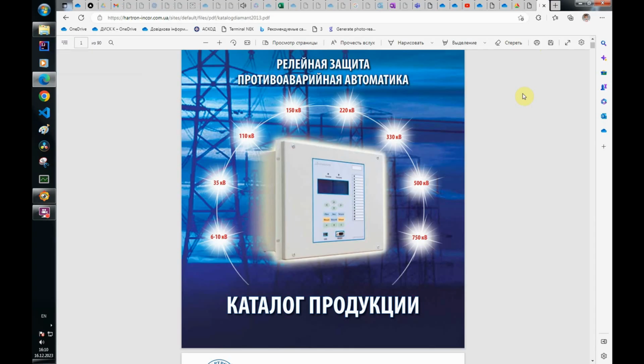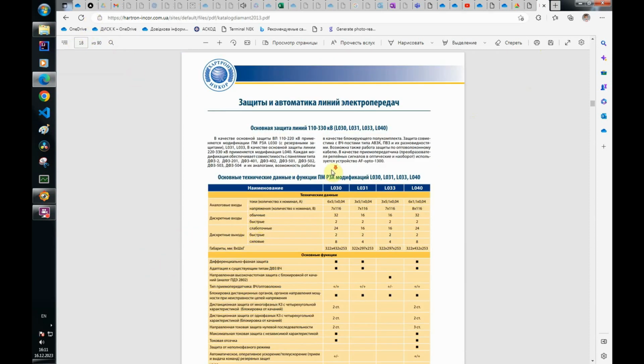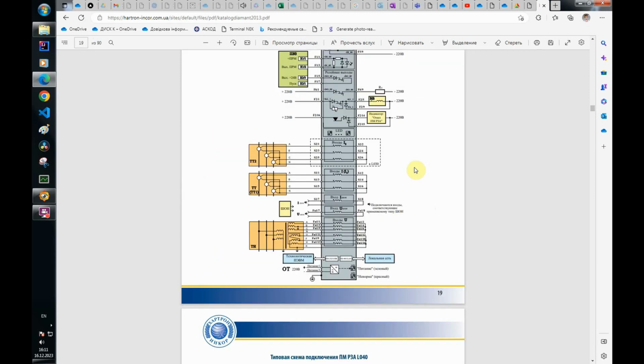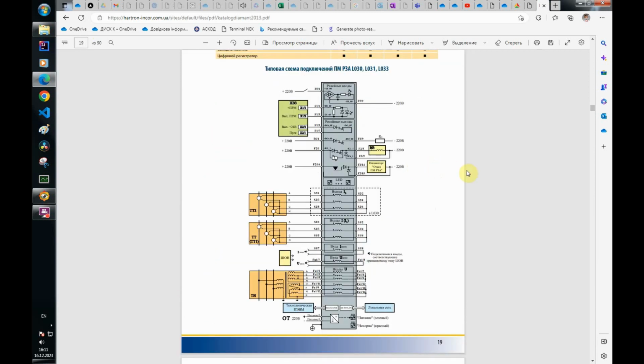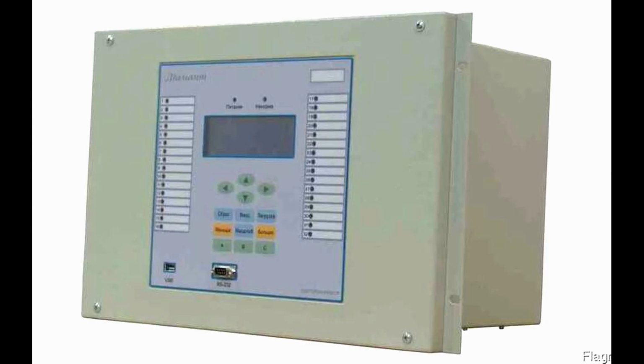I'll open the product catalog. In the case that I will consider, the L030 device is used. This is an IED that performs the functions of phase differential protection and backup protection. The set of backup protections for the device is limited: 2 zones of distance protection, 2 steps of zero-sequence current protection, and current cutoff. There is a function for backing up breaker failure and reclosing.